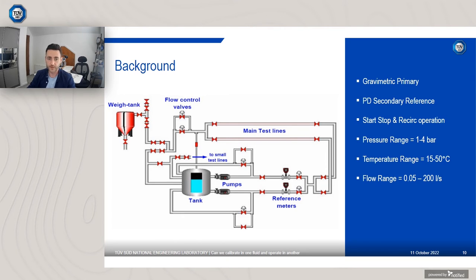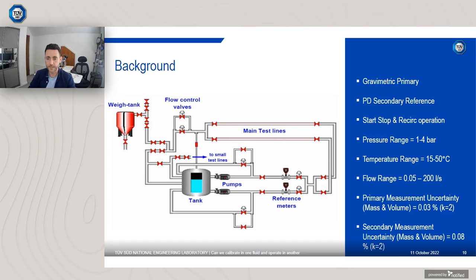In the flow range, it's larger than the EPAT facility. We can go from 0.05 to 200 litres per second. We're fully accredited. Our primary uncertainty is lower. It's 0.03% at the 95% confidence level, so that's going to the weigh tank. And if we use our secondary reference master meters, the uncertainty for mass and volume, similar to EPAT, is 0.08% at the 95% confidence level.